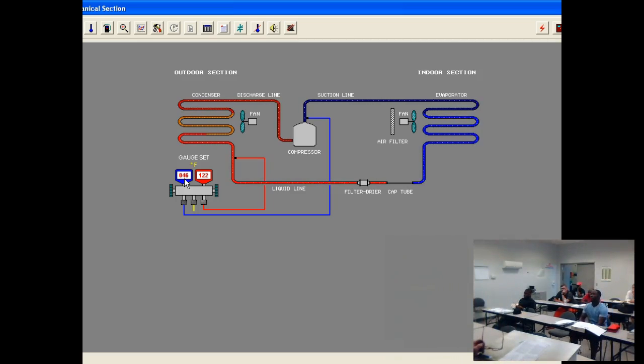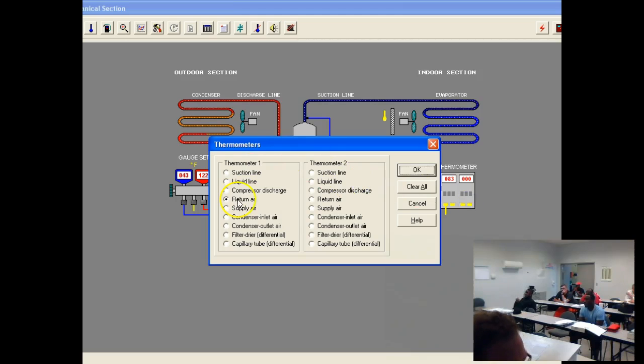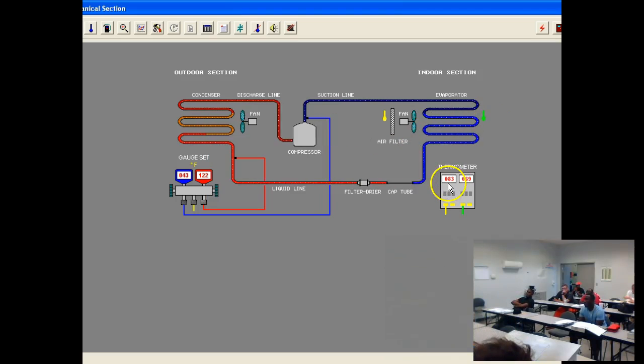Okay? That's pretty easy. I'm just going to go through these tools real quick. The next one is temperature. We have two temperatures. You can't tell on this, but one is yellow and one is green. These are the different places you can measure. I've got one on the return air, and I'm going to put supply air on the other one. One is 83 and one is 68. Like I said, you can do it in a number of places. So we can get superheat, subcool, and delta T here.